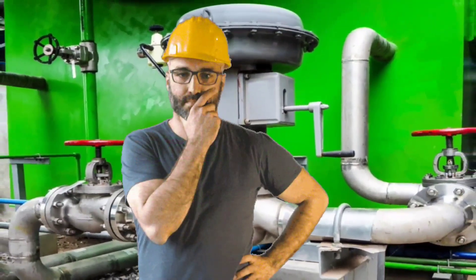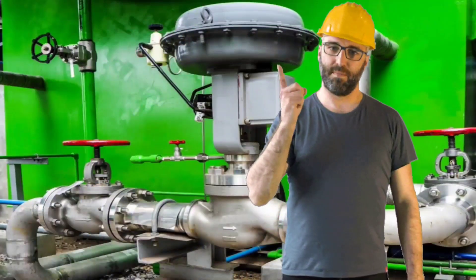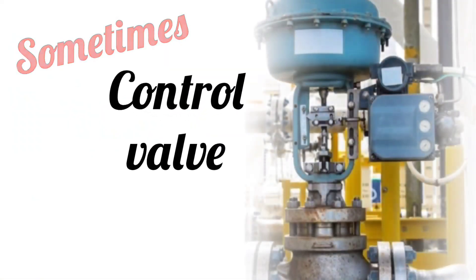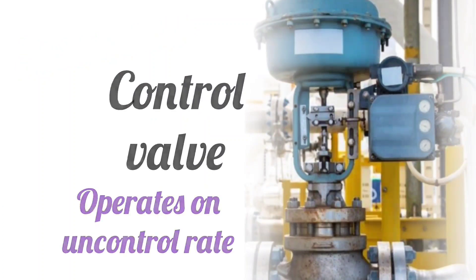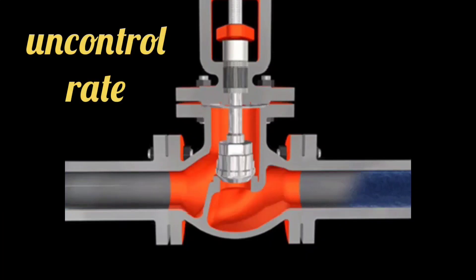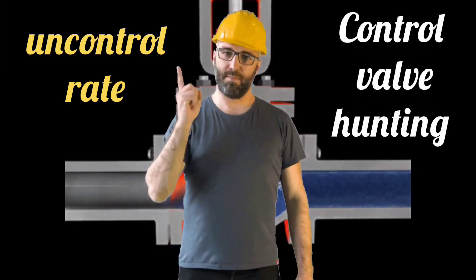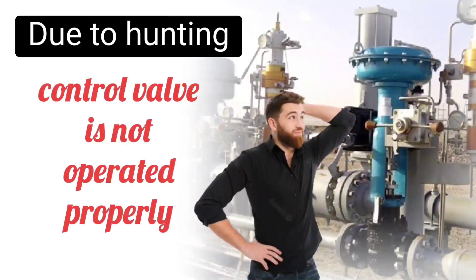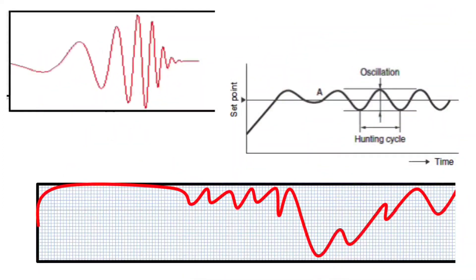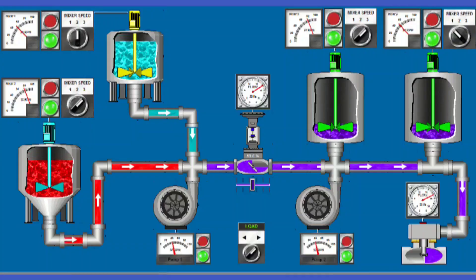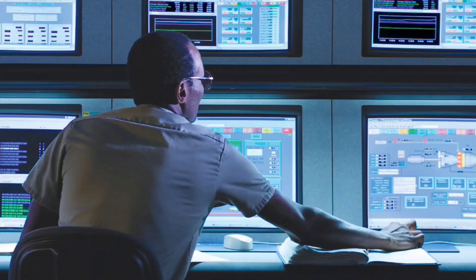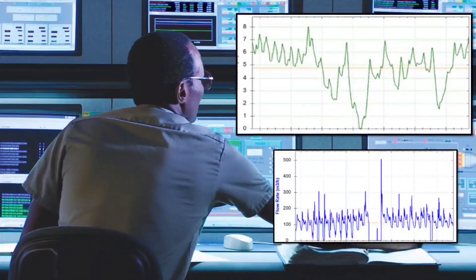Today we are going to discuss a common problem in the control valve. Sometimes the control valve opens and closes at an uncontrolled rate. When the control valve opens and closes at an uncontrolled rate, it is called control valve hunting. From control valve hunting, the control valve does not operate properly and the process variable changes randomly. This can cause process disturbance. If you see the trends on SCADA, you will see this type of trend.